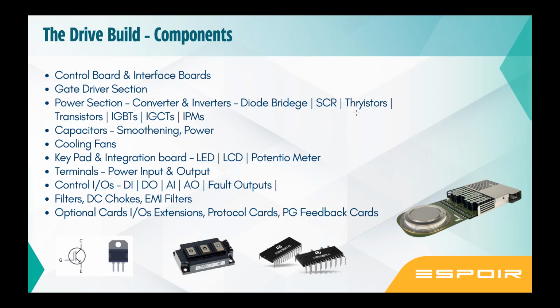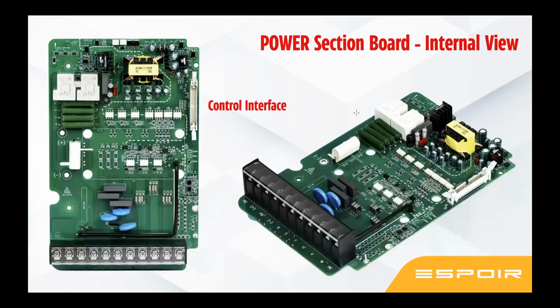Filters, DC choke, EMI filters. Option cards like IO extension cards: if you need more IOs, you can buy an extension card. If you need Profibus or Ethernet cards, by default most drives come with Modbus. If you need Profibus, Profinet, Ethernet, EtherCAT, Mechatrolink, all those options are available as protocol option cards. You need to check what is available from a particular brand. Some brands don't have an option card, then you need to change the brand. PG feedback card, pulse generator, encoder feedback cards. And just to give you a few pictures for reference.